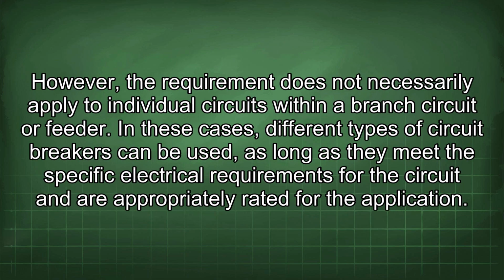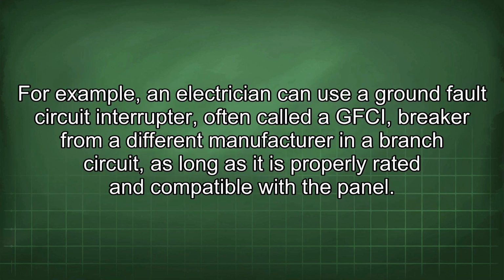However, the requirement does not necessarily apply to individual circuits within a branch circuit or feeder. In these cases, different types of circuit breakers can be used, as long as they meet the specific electrical requirements for the circuit and are appropriately rated for the application. For example, an electrician can use a ground fault circuit interrupter, often called a GFCI, breaker from a different manufacturer in a branch circuit, as long as it is properly rated and compatible with the panel.